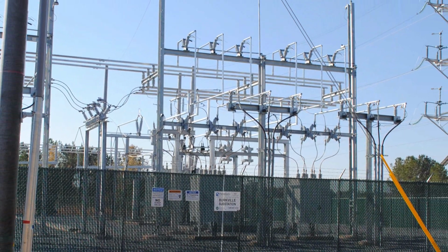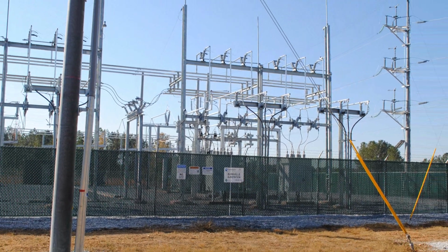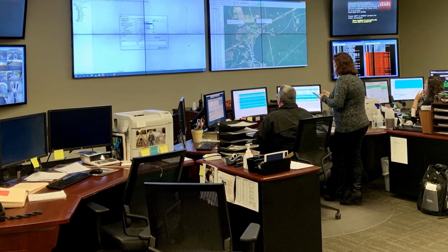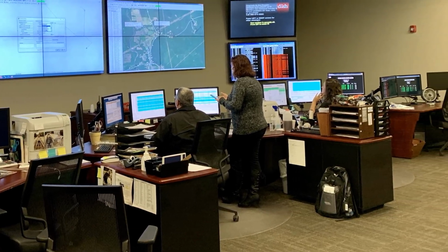Once the transmission is connected to our substations, we can begin our restoration process on our side, focusing on the substations themselves. If we've had the high side protective device open, or if we've lost communications completely with the substation, we have to physically send somebody there to see what's going on and get eyes on it. If we've lost communications, our IT and engineering groups work in the background to try to restore them so we have visibility in our dispatch center.